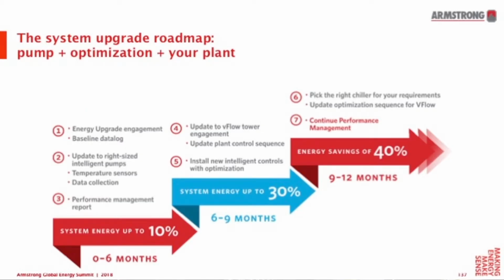So in summary, and I shared this slide earlier today, you start with the pump, you save 10%, learn from the flow and all the intelligent analytics that the pump generates. Then take the next step, which is primarily, from our experience, upgrading the towers or converting them to variable flow, giving 30% of energy. Then you go to chiller optimization or chiller resizing, and that gives you another 40% of energy.